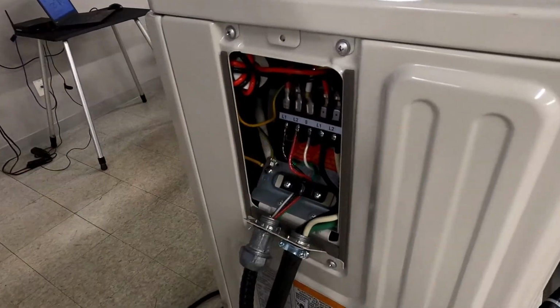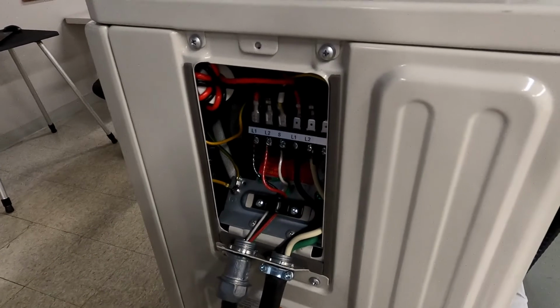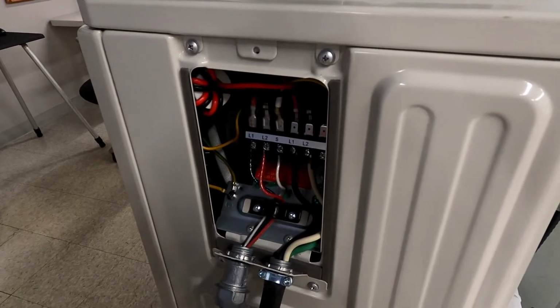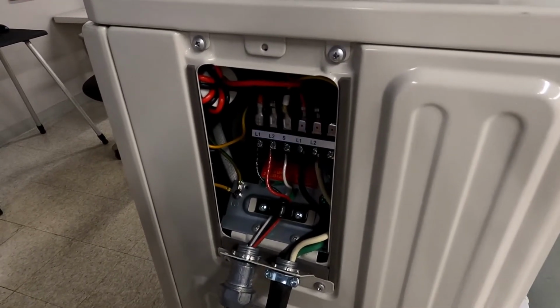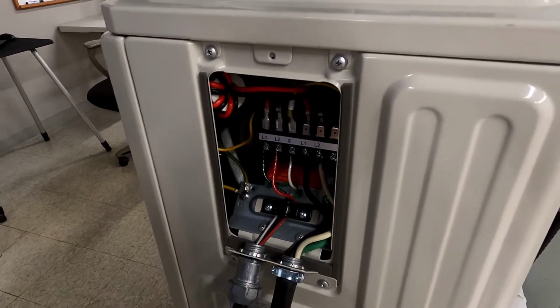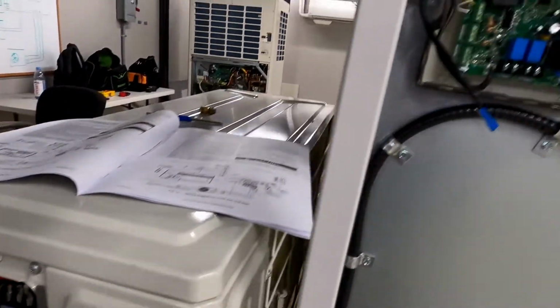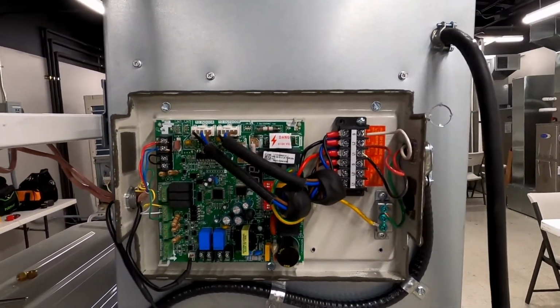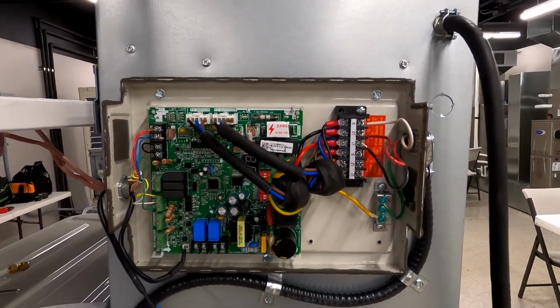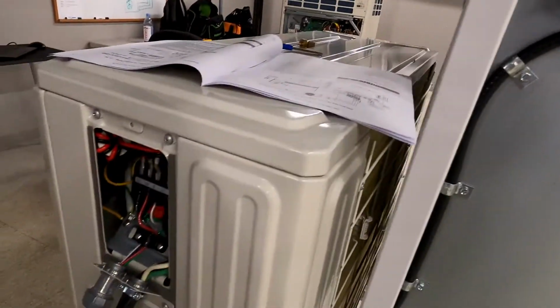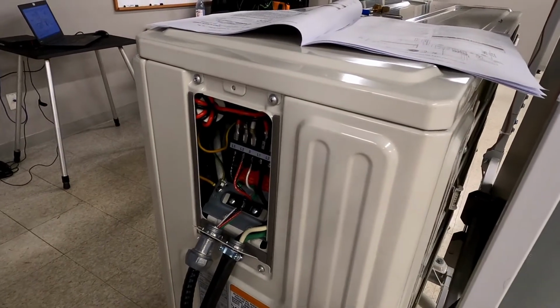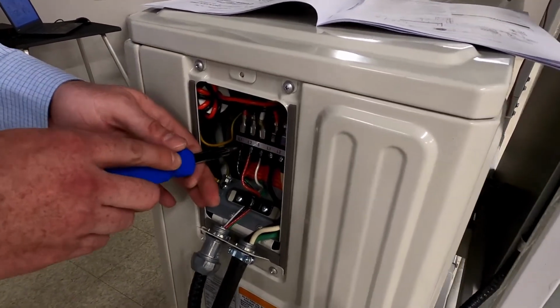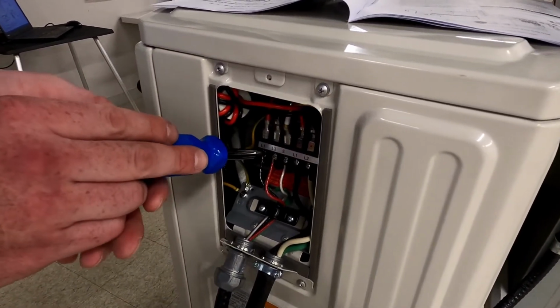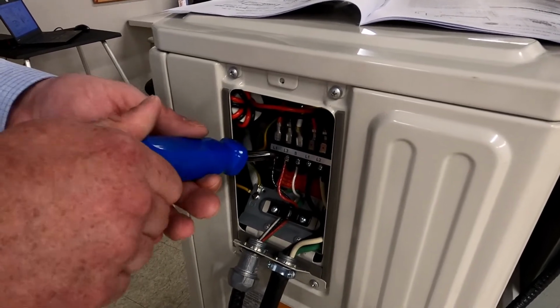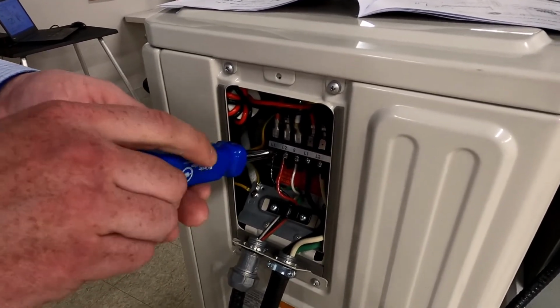All right, now we're going to hook up our interconnecting high voltage communication wire between the ductless outdoor unit and the 24 volt interface kit. This is necessary so that the 24 volt interface kit can control the speed and refrigerant flow of the ductless unit outside and also tell it what mode to operate in. It's important that we use 14 gauge stranded wire when hooking this up to avoid any possible communication issues.